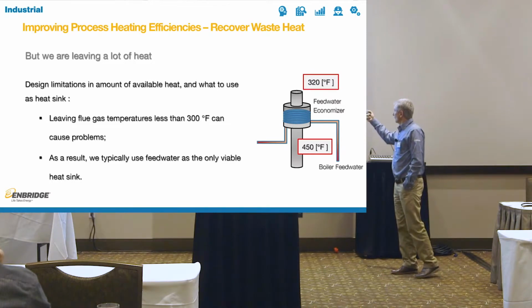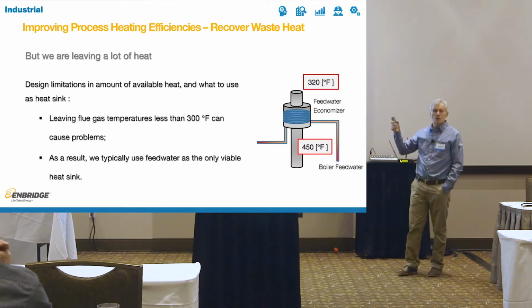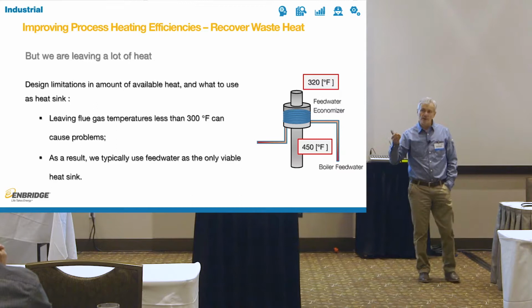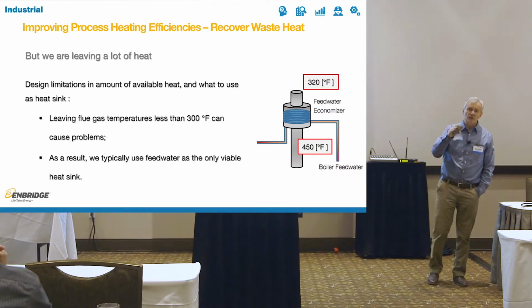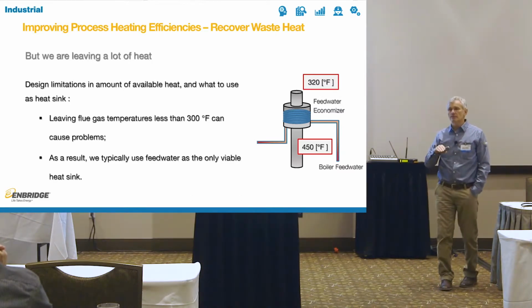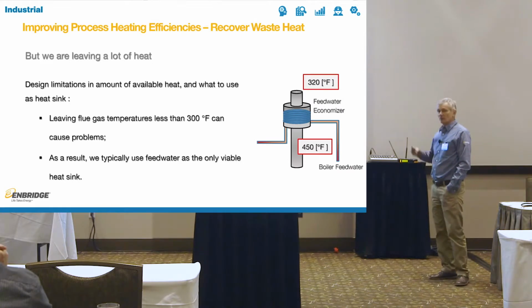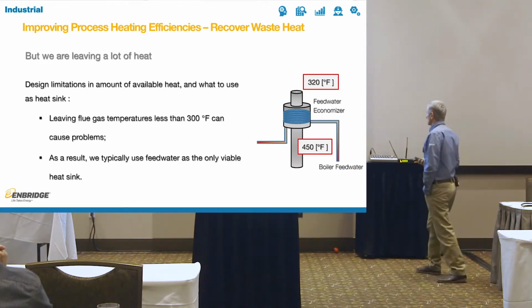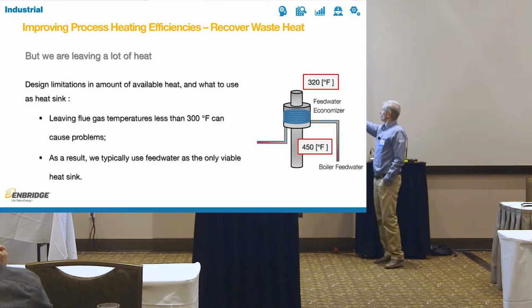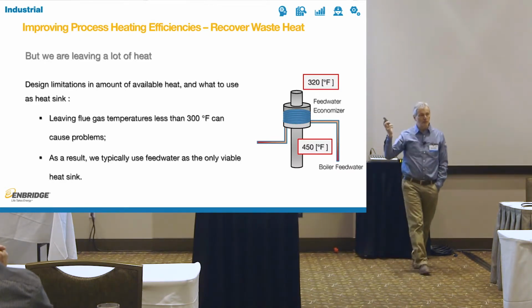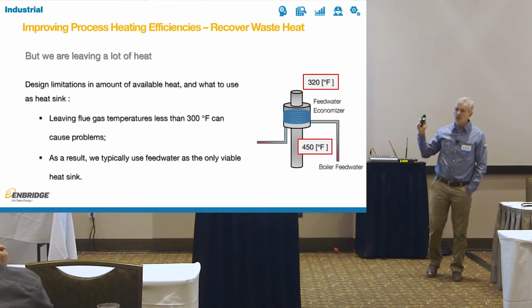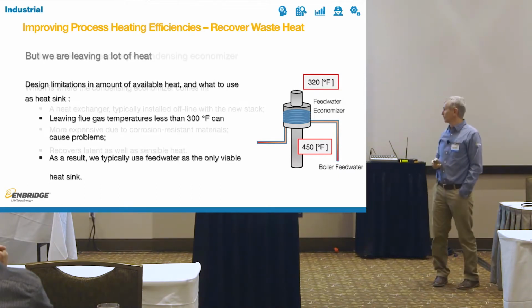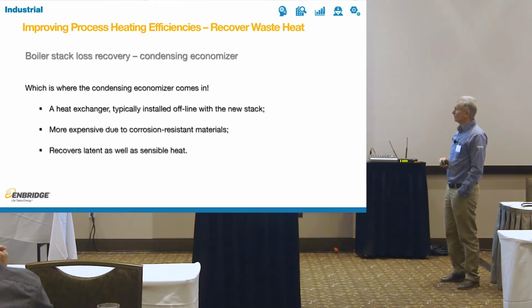So the only thing that can be put through the Feedwater Economizer is the boiler feed water, because it's the only thing warm enough, or not cold enough. That's why you're leaving a lot of heat. If you were to put something cold through here, you would condense and ruin your Feedwater Economizer, and that would be the end of the story. So you're leaving a lot of heat still available going out of the stack.